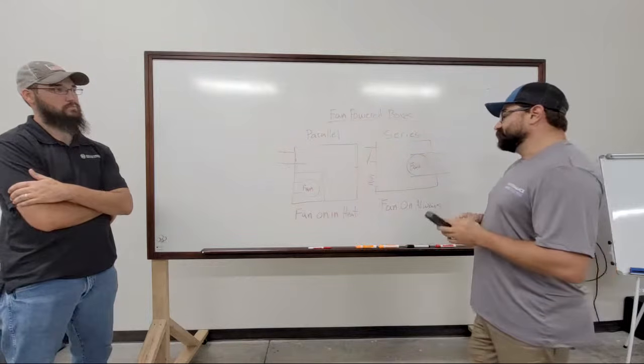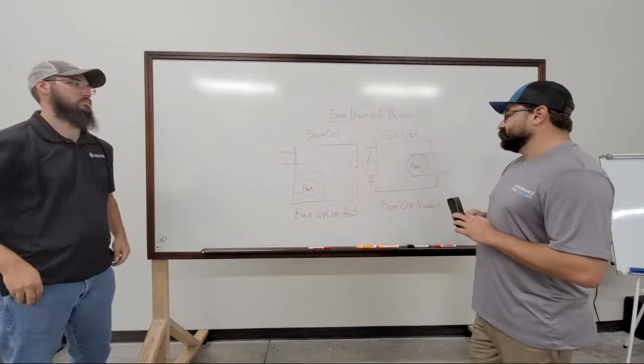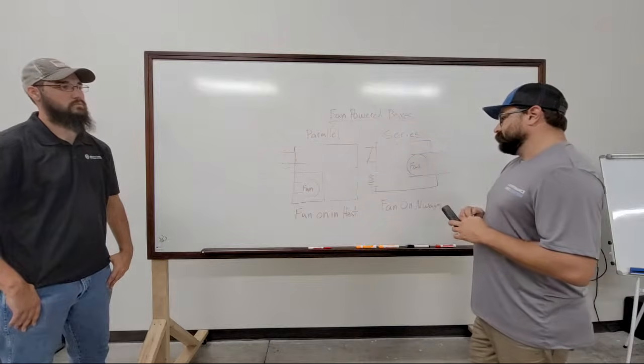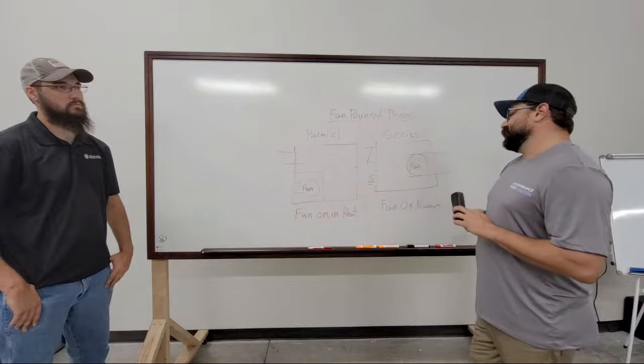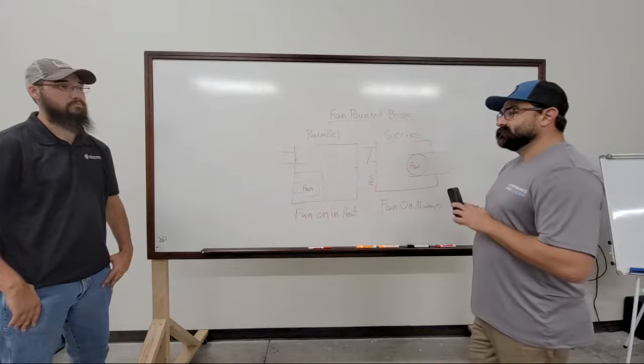So it's one benefit of series over parallel, along with the energy savings side of it. I guess you could say there'd be less wear and tear on the fan because it's not starting and stopping on your contactor as much. Good benefit.